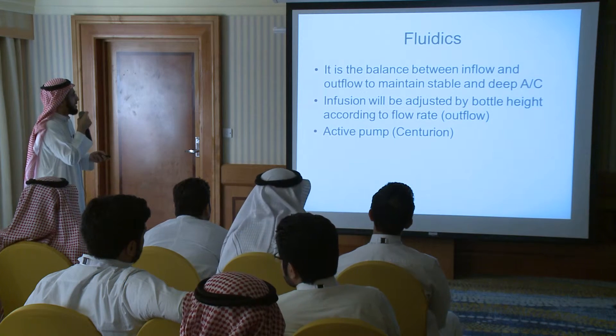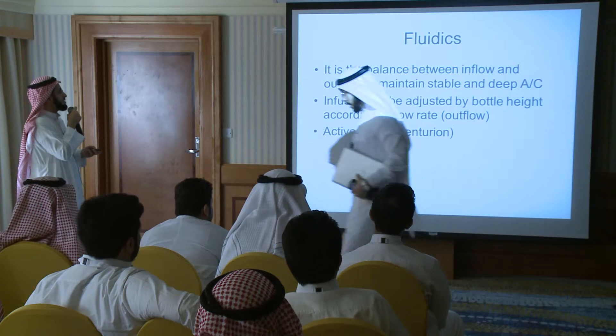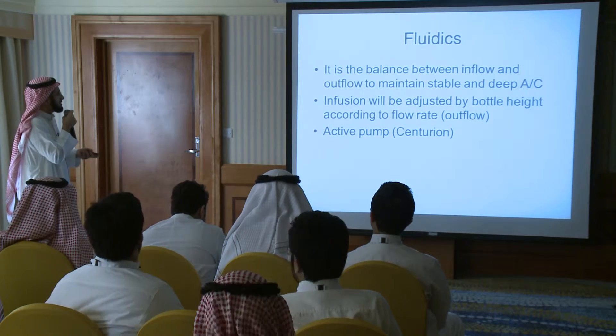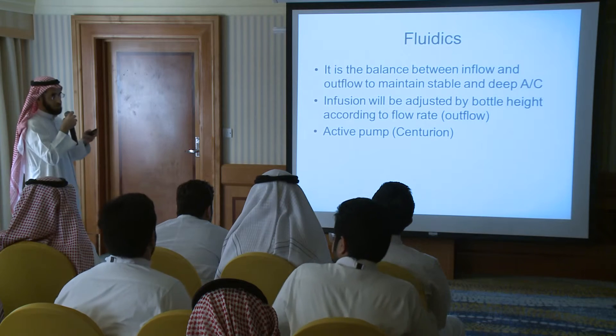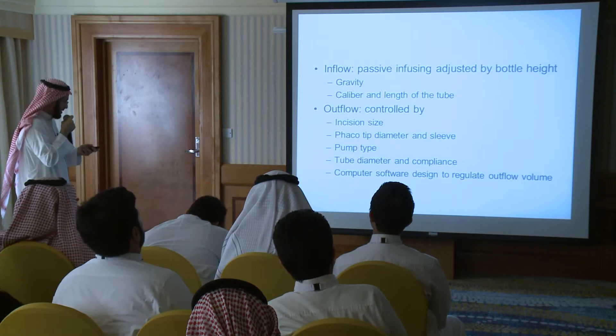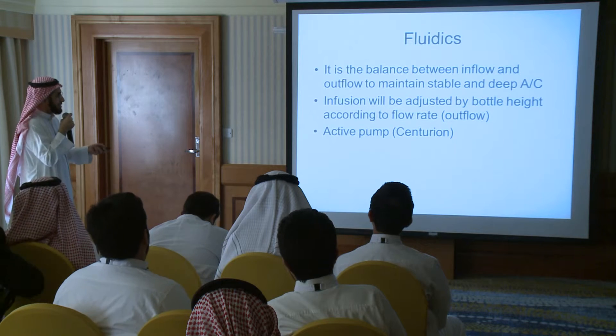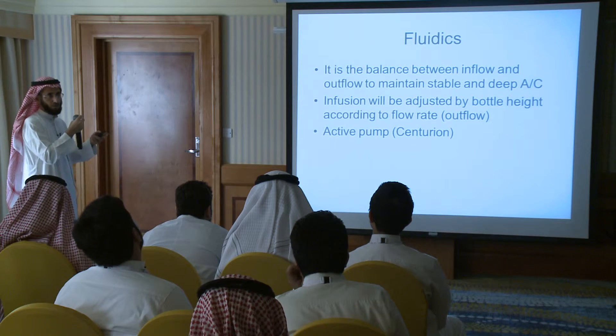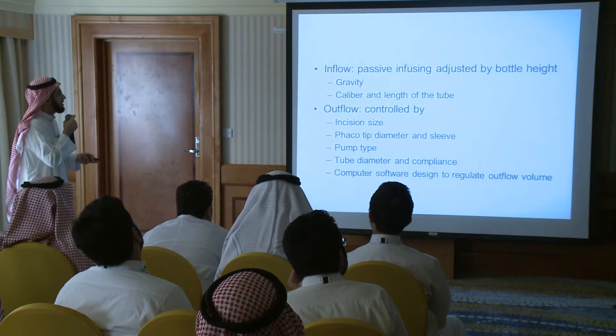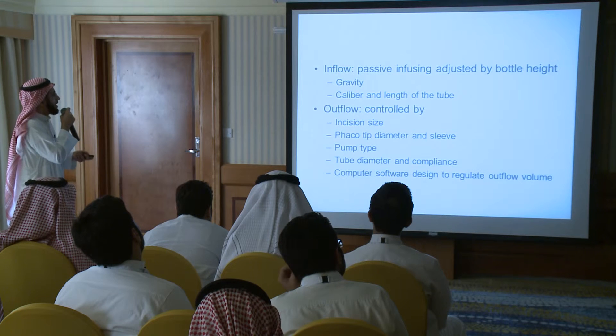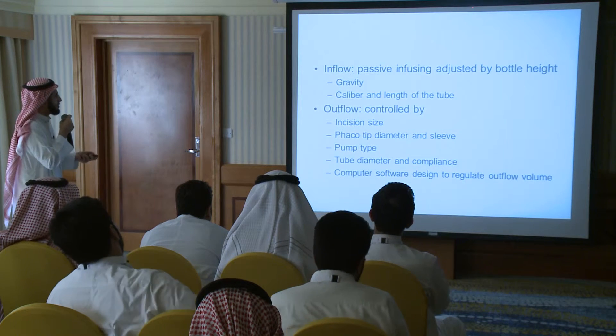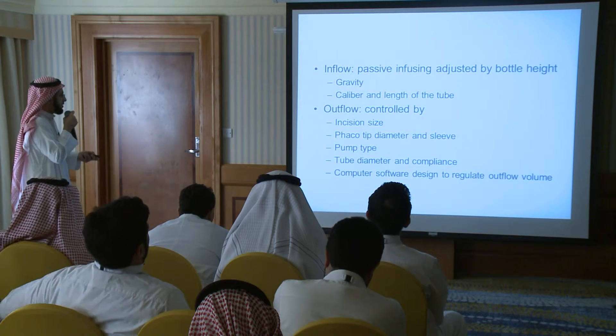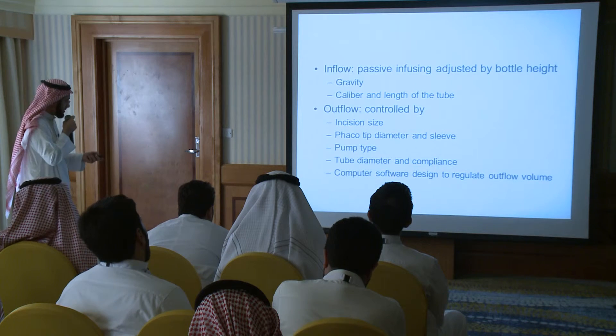I'll mention a few things about fluidics, which is the balance between inflow and outflow. The infusion is adjusted by the bottle height according to the flow rate — this is very important to maintain the anterior chamber. Some machines, like the Centurion from Alcon, have an active pump with a sensor at the tip of the phaco that adjusts inflow to the anterior chamber. Most machines use passive gravity to maintain the chamber. The outflow is also important and will be mentioned later.